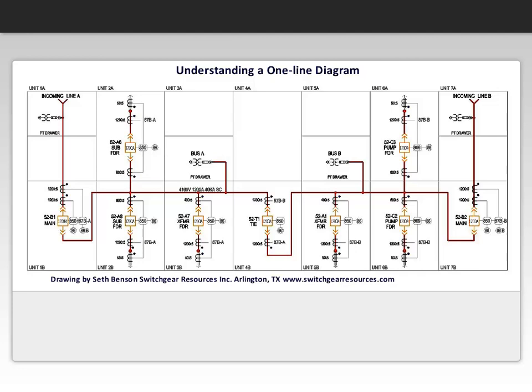First, let's do an overview of what is being displayed. This is a 7-structure medium voltage switchgear double-ended lineup with 2 incoming line feeds and a tiebreaker. This is also referred to as a main-tie-main setup. You can see the main breaker for incoming line A in structure 1. The tiebreaker is in structure 4, and the main breaker for incoming line B is in structure 7. You can follow the power flow by the red line from the incoming section through the top or line side of the main breaker, through the main breaker, to the load side or bottom of the main breaker where the switchgear's main bus originates. The bus distributes the power to structures 2 and 3 and then to the feeder breakers.